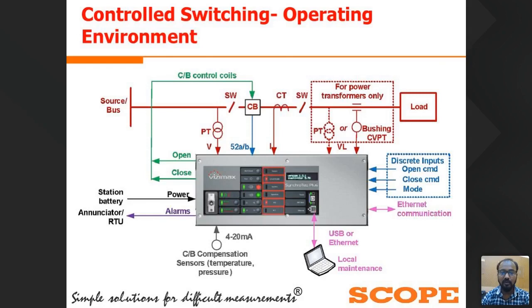We can configure the compensations in the CSD configuration, so that the CSD can get the data from the sensors and automatically compensate the breaker operating time as per the present condition. At the time of configuring the CSD, we put in the breaker operating time by doing the timing test, and after that we do not need to change the breaker operating time every time. The CSD will automatically calculate it using this compensation data. So we are taking the inputs from these CSD compensation sensors.